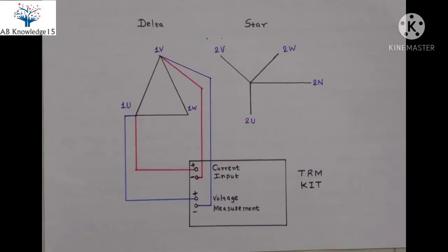Here in this figure we have, for example, taken a transformer whose primary is delta winding and secondary is star winding. Primary side winding is denoted by 1U, 1V and 1W, whereas secondary side winding is denoted by 2U, 2V, 2W and neutral point. Below is shown a TRM kit, transformer winding resistance measurement kit, which has 4 terminals, 2 for current injection and 2 for voltage measurement. The connection of the TRM kit with the transformer winding is shown, supposing we have to measure winding resistance of the primary side for the 1U and 1V terminals.